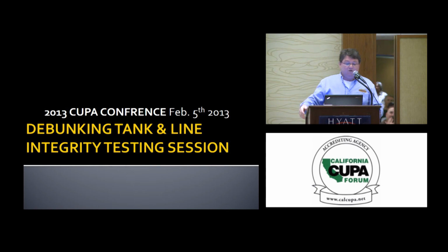Some of our keys. We would measure the air pockets. Our system calibrates every single line. I have a fingerprint of every single line we've ever tested. I can tell you what the resiliency is. I can tell you what kind of air pocket, what kind of sensitivity I have. Because every installer from the 60s on always made 1/8 inch back. No, they do this sometimes. So we'd have entrapped air pockets. That messes up mechanical and electronic leak detectors, by the way.